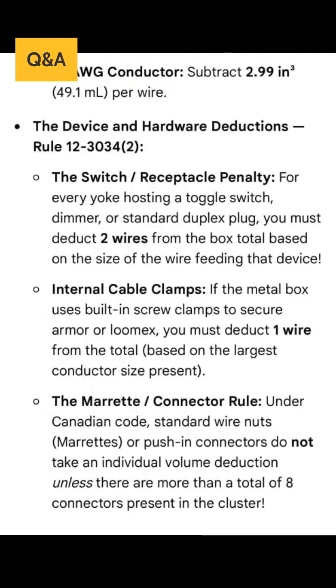Now we go on to the Marrettes connector rule. Under Canadian codes, standard wire nuts, Marrettes, or push connectors do not take an individual volume deduction unless there are more than a total of 8 connectors present in the cluster. Now we're going to go over to the other part of that, which is the actual NEC rule.